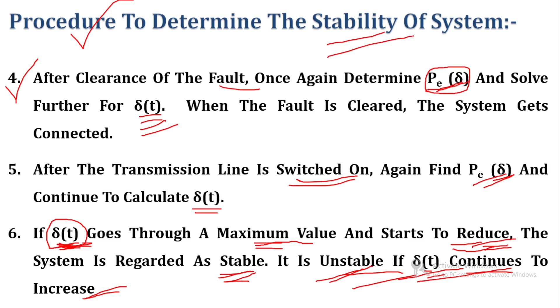So we have a simple logic: before the fault we calculate the power transfer as a function of delta and the torque angle as a function of time. That is the pre-fault value of power and delta. Then we calculate the power as a function of delta and delta as a function of time during the fault duration, and after removal of the fault again we calculate the power and delta as a function of time. In the data collected before, during and after the fault, if delta of t goes through a maximum value and after achieving it starts to reduce, the system is stable. If the value of delta t is continuously increasing, then the system is said to be unstable. That is the procedure to check the stability of the system.